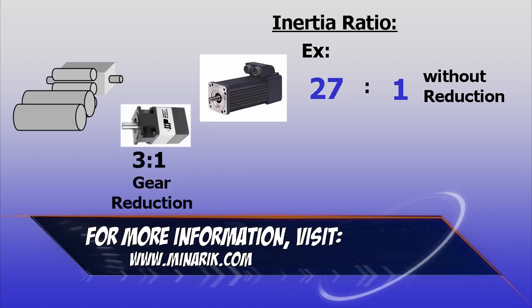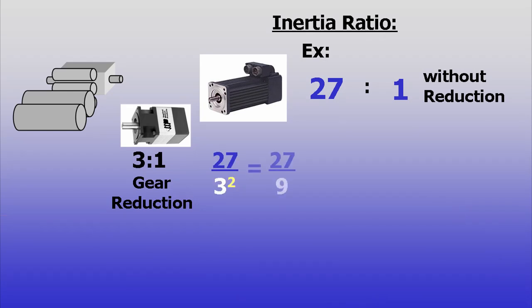If a 3 to 1 gear reducer is added, it reduces reflected inertia by 3 squared, or a factor of 9. The new inertia ratio will go from 27 to 1 to 3 to 1.